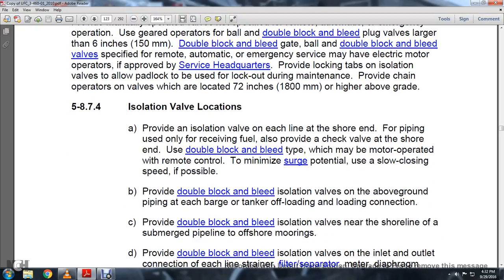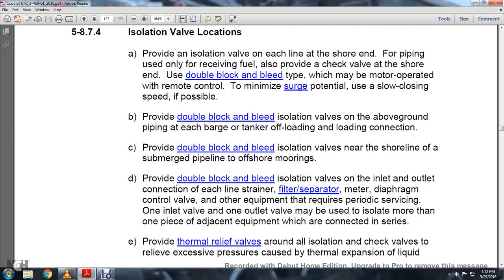5874, isolation valve location. Provide an isolation valve on each line at the shore end of the pipe for piping only receiving fuel. Also provide a check valve at the shore end. Use the double block and bleed type, motor operated with remote controls, to minimize the surge potential by closing the flow as slowly as possible.